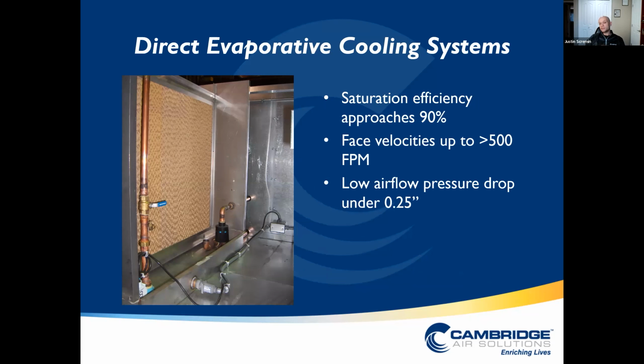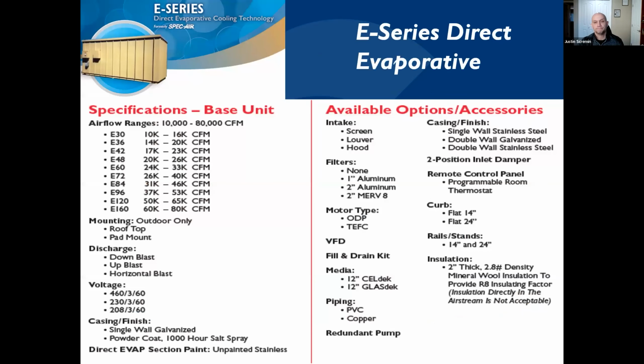And the best method of control is a humidistat in the space. You set it at whatever you want, 50%. When the relative humidity gets higher than 50%, it will shut off the water. We can continue to ventilate the building, but we're going to stop adding that temperature depression or that cooling effect, and we are going to just ventilate. As I said, this is the lowest complexity. So there aren't a whole lot of options available to us in this piece of equipment. It's pretty basic stuff up to 80,000 CFM.